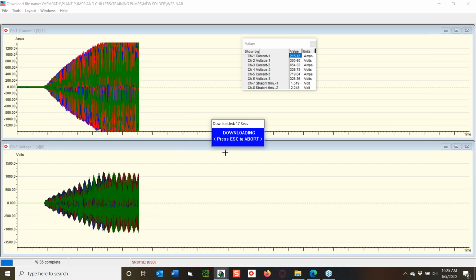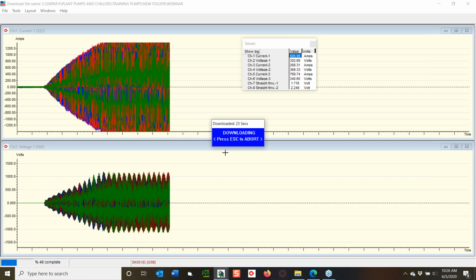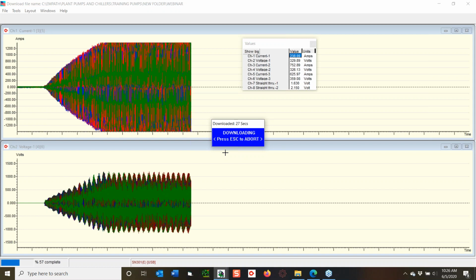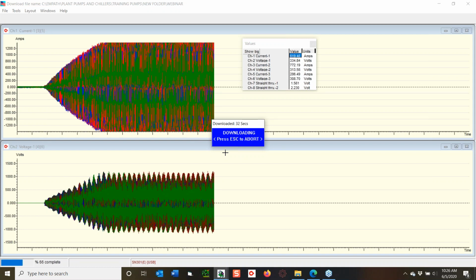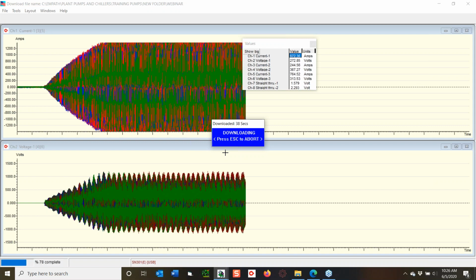And I apparently set the CT ratio a little high. 1200 amps, woohoo! But remember, that's RMS. So what is it saying? Amps is actually coming out to be something less than that. But in any case, yeah, so it's showing a little higher than I expected. But you know what's kind of cool? I can change that afterwards if I need to by changing that CT ratio.